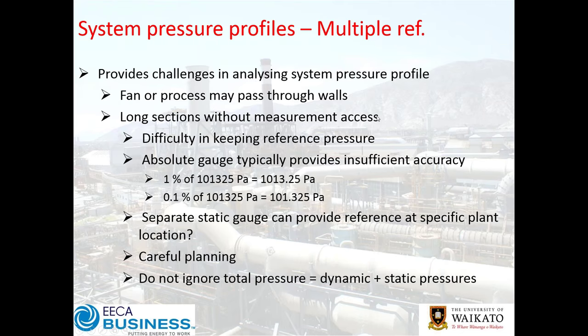One way around this is to measure in absolute pressure, but on an absolute gauge, 1% variation on 101.325 kPa is 1,000 pascals, and 0.1% is still 100 pascals — quite substantial depending on what you're measuring. It's really important to understand what's going on as you go from point to point. When doing measurements on day one versus a future day, verify the reference pressure both outside and in the building. Careful planning may mean you need to also consider total pressure — the dynamic plus static — as another approach.